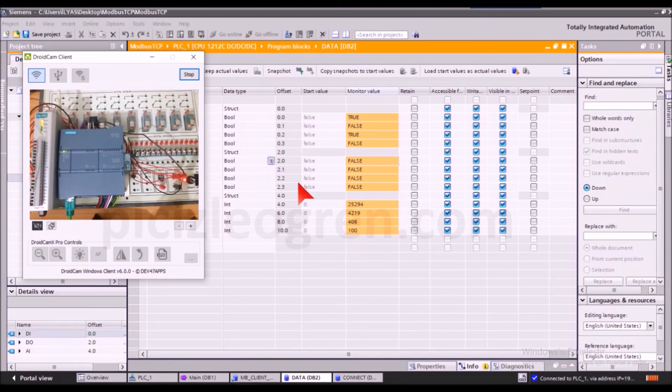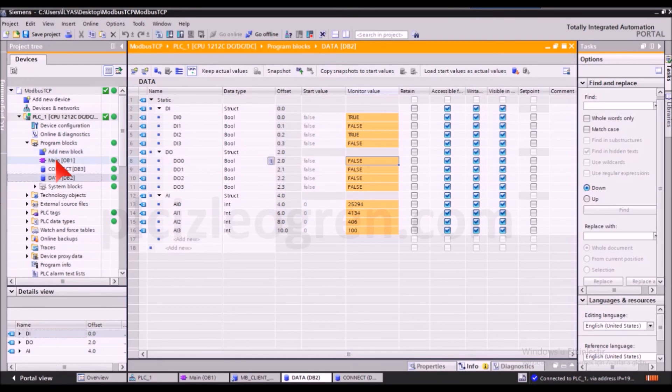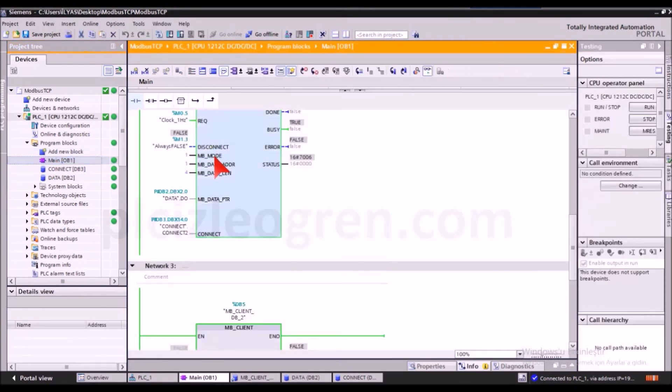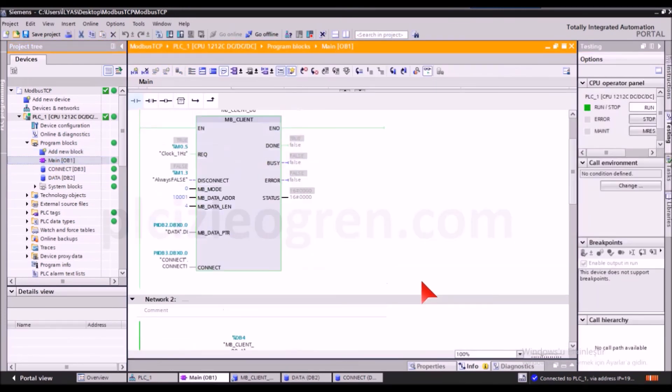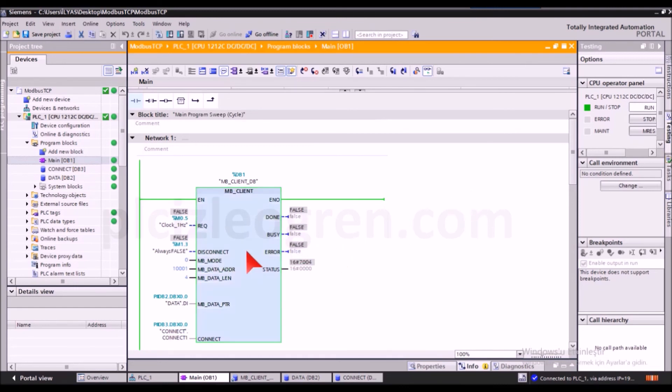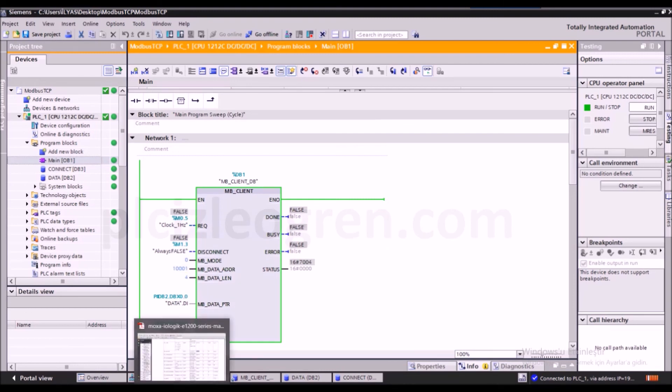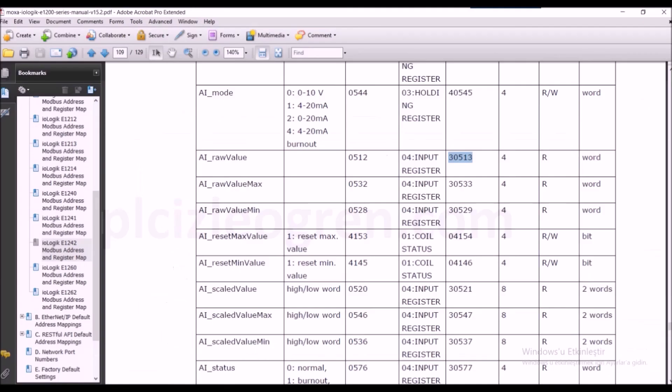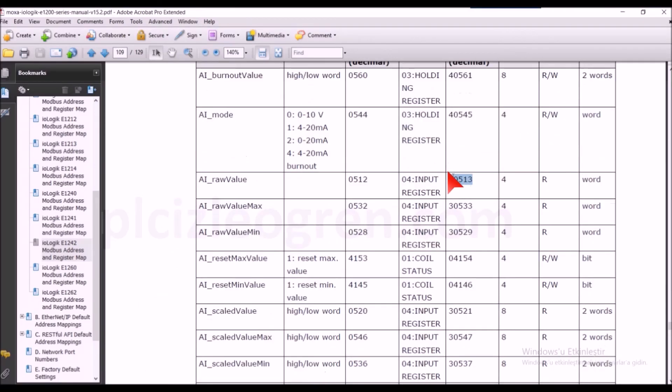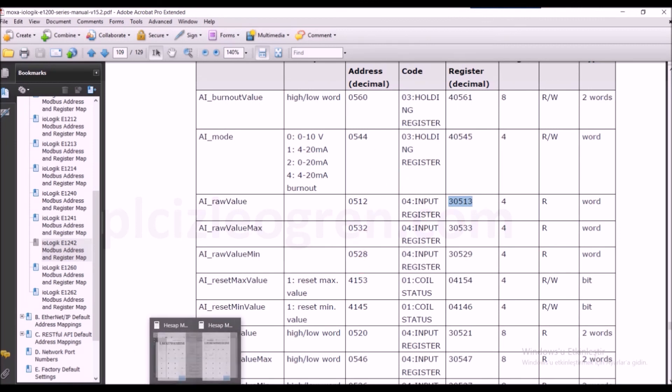Let me summarize this quickly. What do we do first? First, we create data blocks for each data that we will write or read. After taking those data blocks, we look into their Modbus addresses. Then we look for the reading and writing addresses regarding how we will start those data blocks. We look into the data sheets of the device and the help menu of the PLC to see what is what and which addresses we can use. It's a fairly simple task. You'll have to look into the sheets and the help menu.